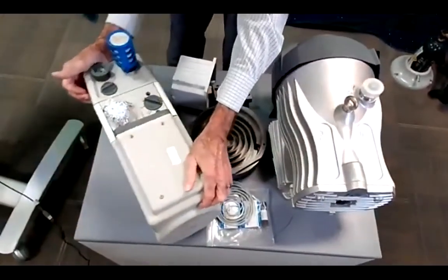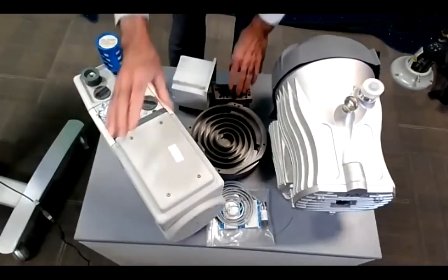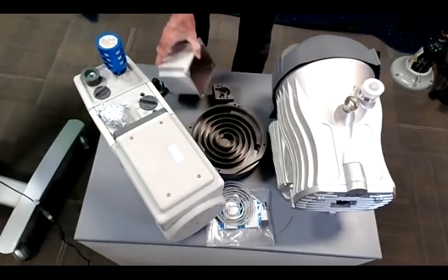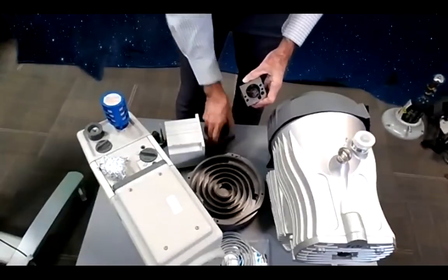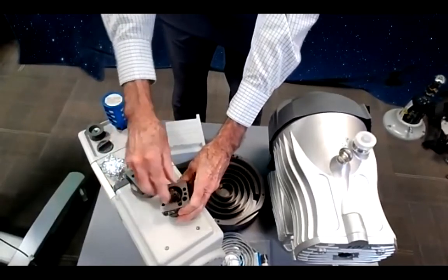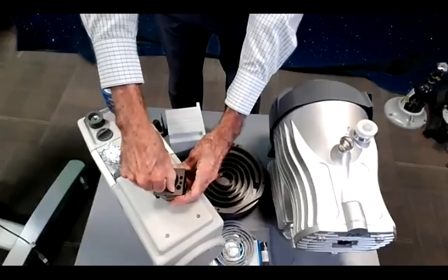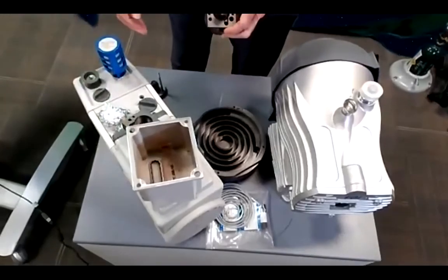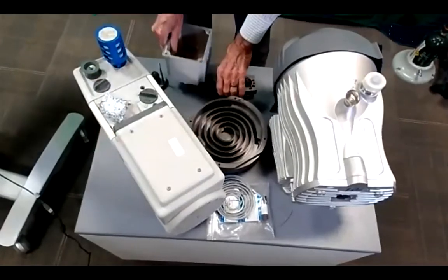This is a direct drive fore pump. Here's your motor and this is the actual pump. The actual pumping area is quite small — this is hard steel. If you look in here, you can actually see the little vane that turns around. The rest of the volume in here is all oil. The oil helps cool this thing; these pumps run hot.